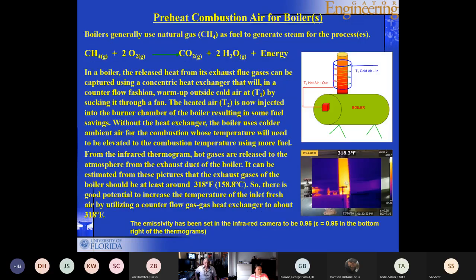This is another assessment recommendation that is associated with boilers, but in this case, we're going to preheat the combustion air that's going into the boiler. Of course, in the boiler, you are burning a fuel, and in the process of burning the fuel, you have to provide air, which has oxygen in it. That air is cold. That air is coming from the ambient, and it's much cooler than the temperature that the air is going to eventually achieve. Now, if you can preheat that air, you can actually save quite a bit.